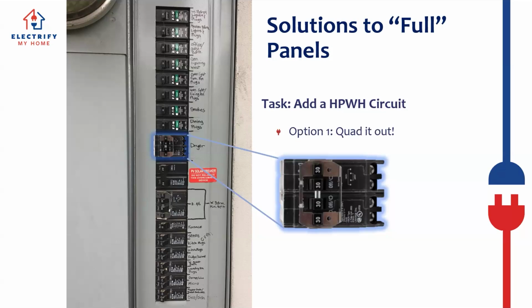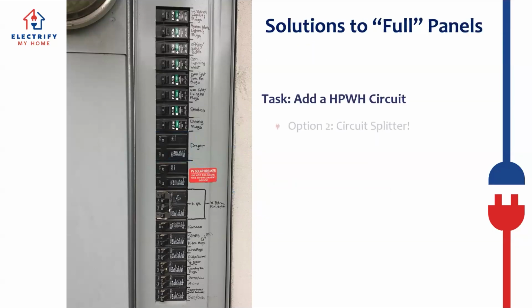Option number one: quad it out. We can add a quad breaker, which has narrow slots that can fit in place of the existing 2-pole 240 volt breaker in the panel. This is a great space-conserving option if the panel is compatible with quad breakers. Of course we need to do our panel calculations to ensure we can add a new breaker to begin with, but this is a great way to alleviate space issues.